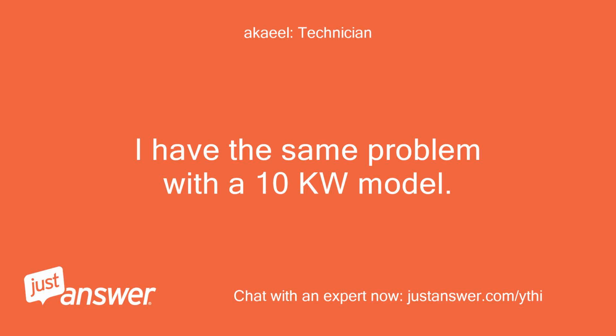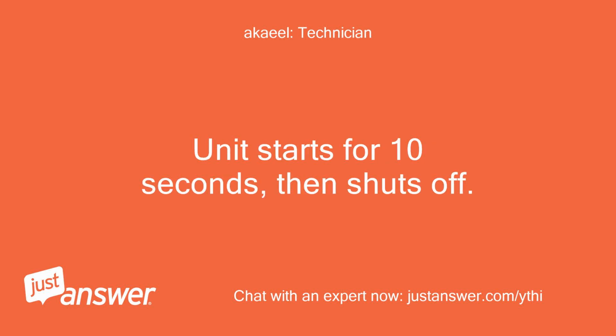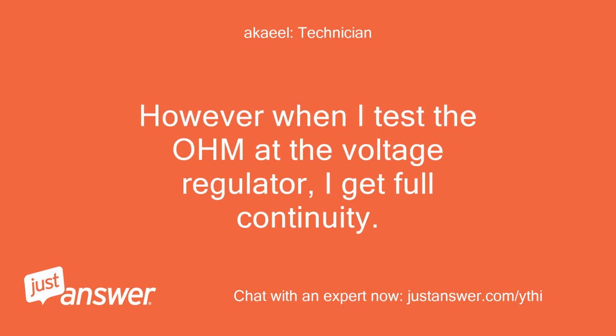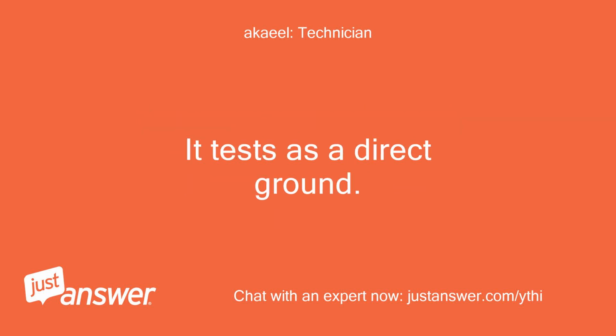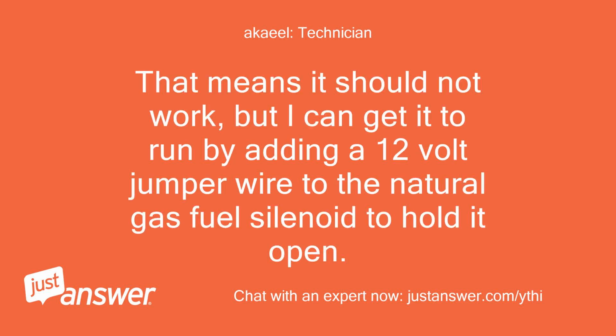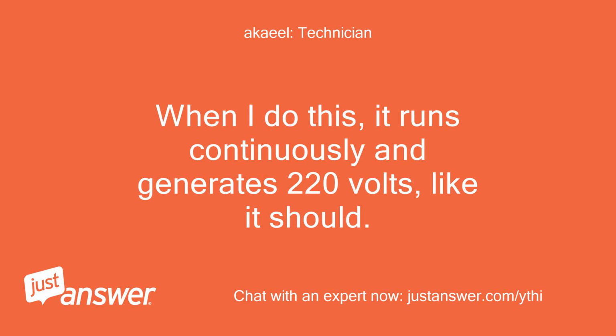I have the same problem with the 10 kW model. The unit starts for 10 seconds, then shuts off. However, when I test the OHM at the voltage regulator, I get full continuity. It tests as a direct ground. That means it should not work, but I can get it to run by adding a 12-volt jumper wire to the natural gas fuel solenoid to hold it open. When I do this, it runs continuously and generates 220 volts, like it should.